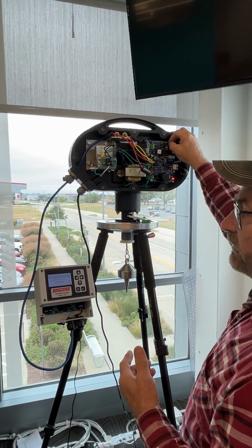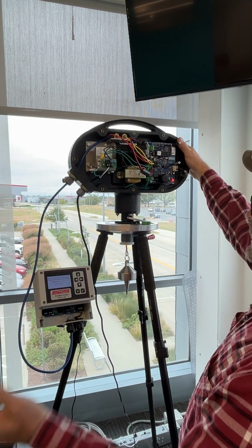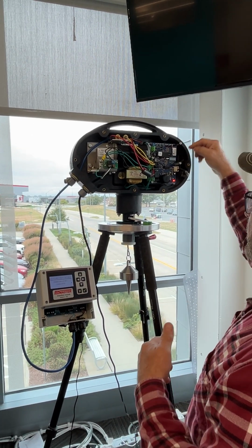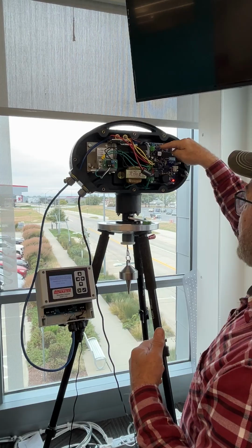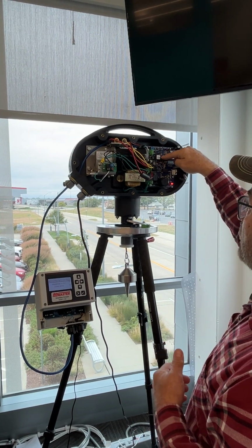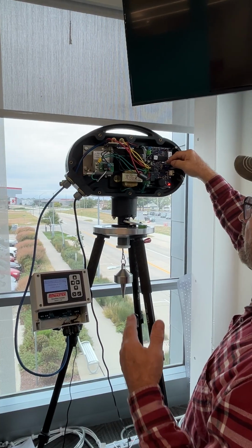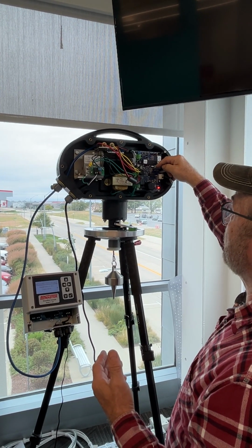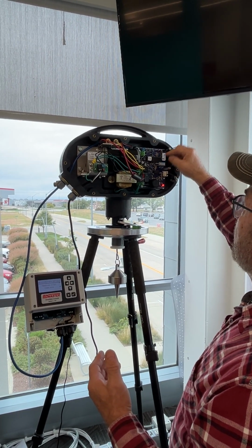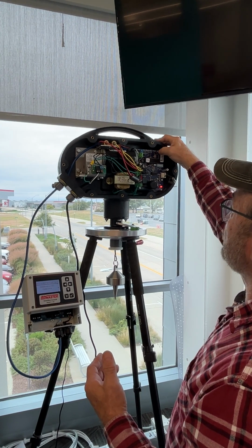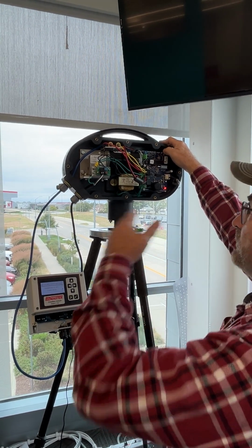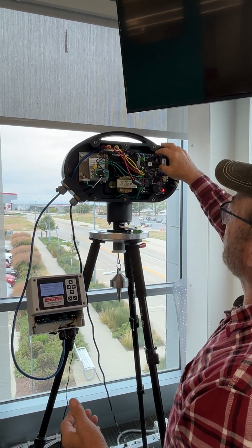The busy light will flash for any measurement request to any address. If that measurement request is for its address, it's going to look at the address switch to see that yes, that's a request for my address.